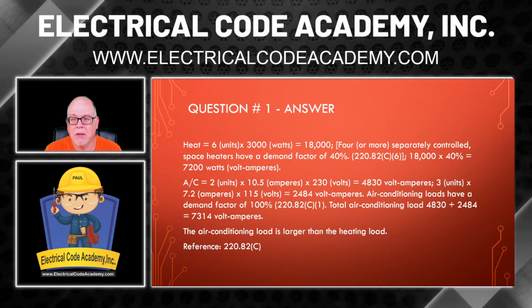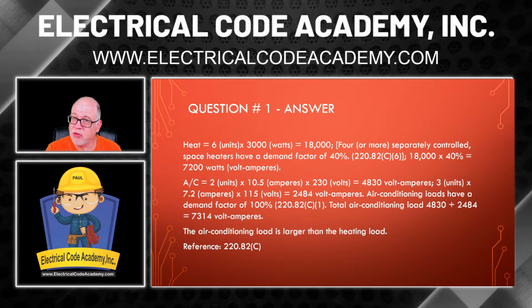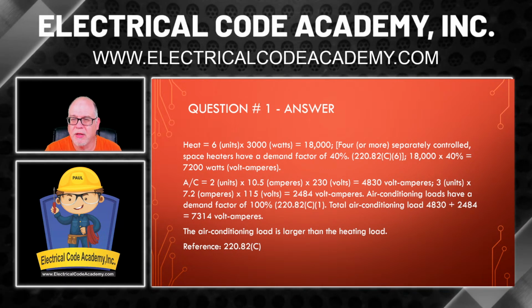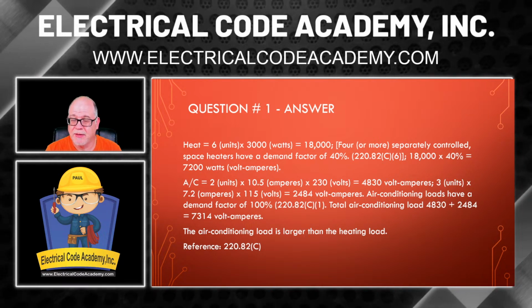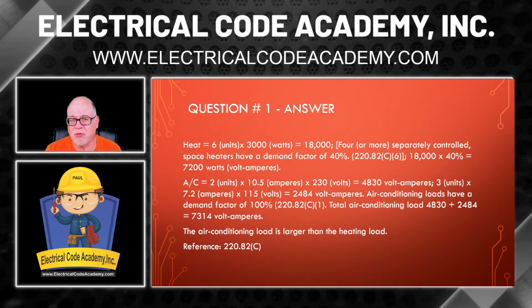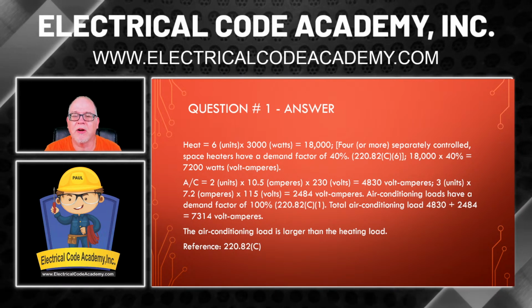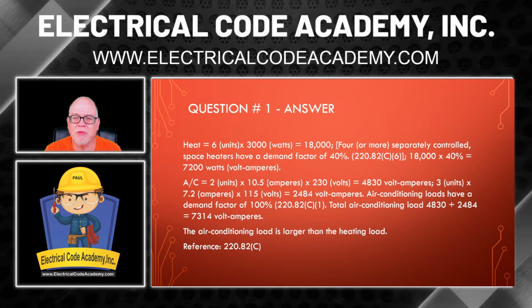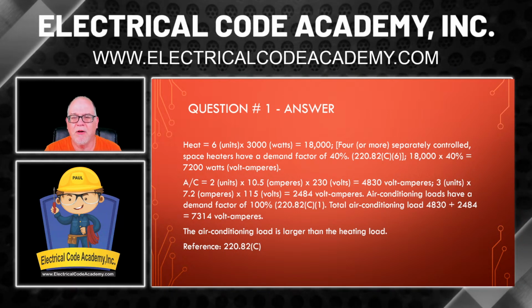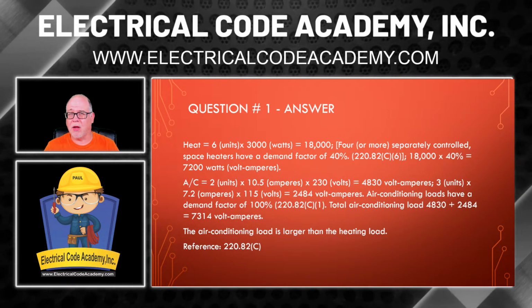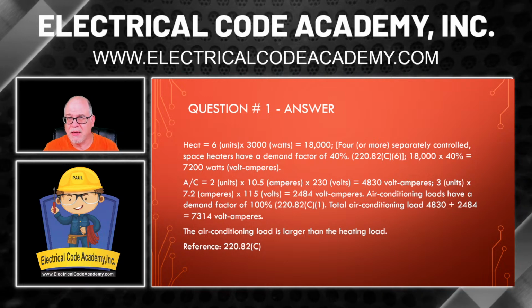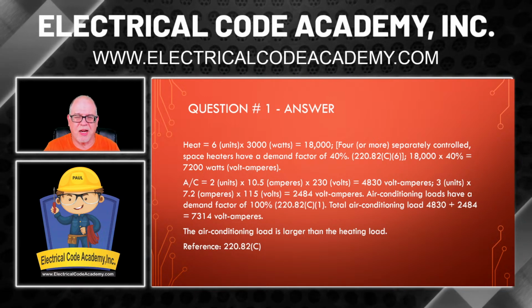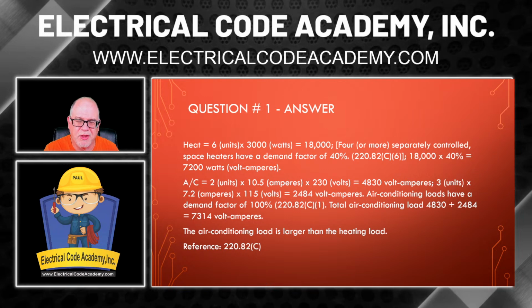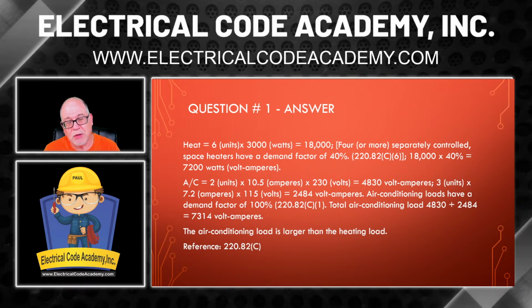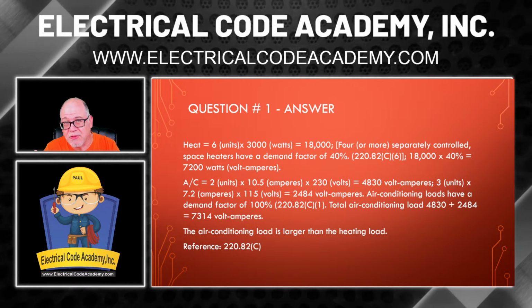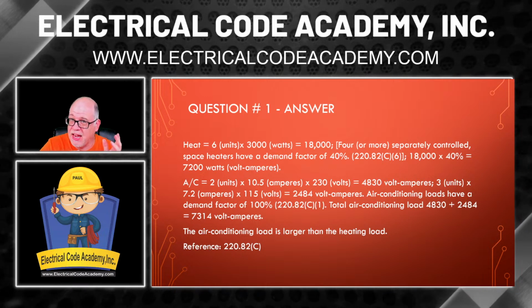Okay? Now let's do the 3 7.2 amp air conditioning units. That would be 3 times 7.2 times 115 volts. That is 2,484 volt amperes. Remember Ohm's law, in order to find VA, what we're doing is it's synonymous. We're just going amps times volts equals watts, and watts is synonymous with VA.